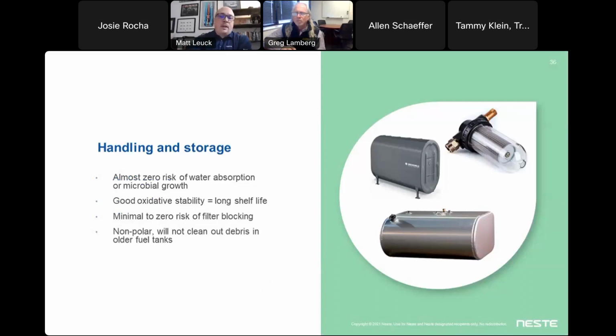This is one of the best parts for power generation. Fuel has to get stored in a tank, and these tanks have to be vented to atmosphere for pressure equalization, which means you get moisture in tanks, so you have to have water separators and do water drains. By nature of the chemistry of renewable diesel, it does not hold on to that water - it repels it very strongly down to the bottom of the tank, which makes it really easy to get rid of. Whereas some other fuels will actually bond up with the water, which can encourage microbial growth and other things that plug filters and cause issues.